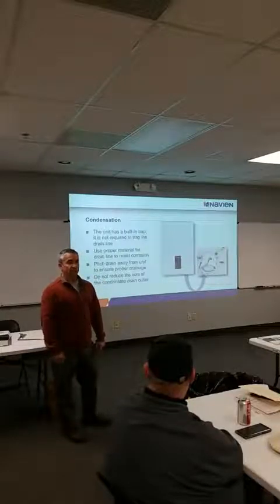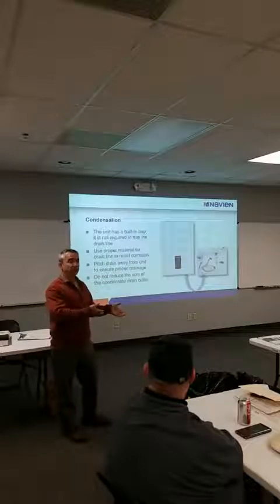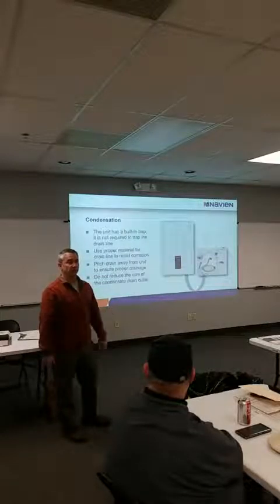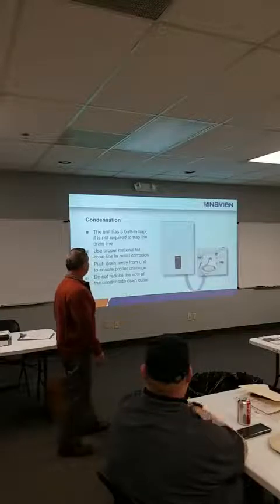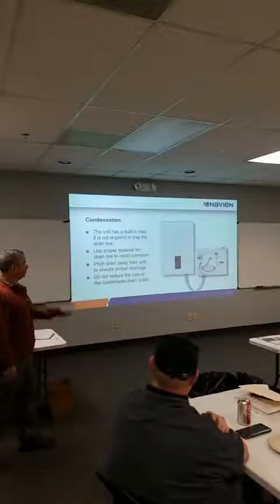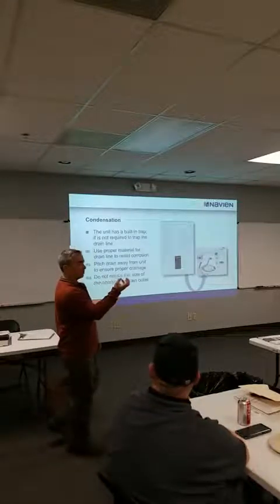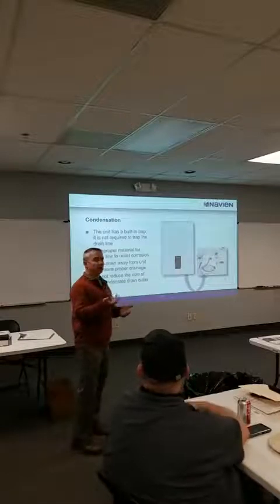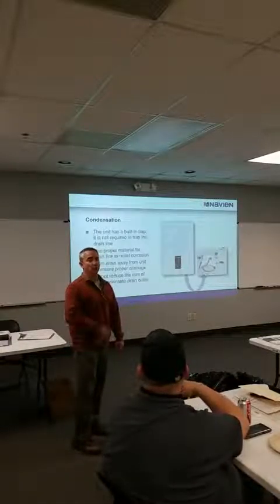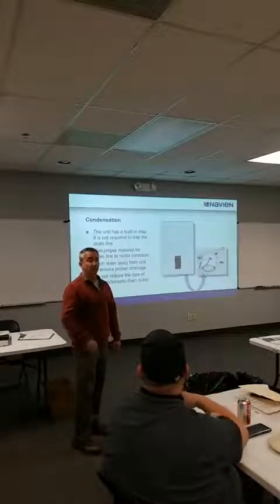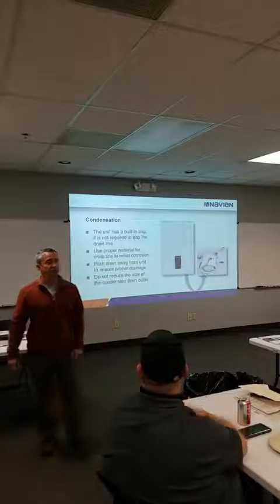Neutralize it. It's acidic enough that it'll mess up the bacteria in your septic tank, especially if you're dumping your furnace into the same drain. It's going to look very similar, just a little cup. You pop that cup and you get about a 1/2 pint of water out of it. If you get more than that, then it's probably plugged up and it's storing water in that heat exchanger somewhere.